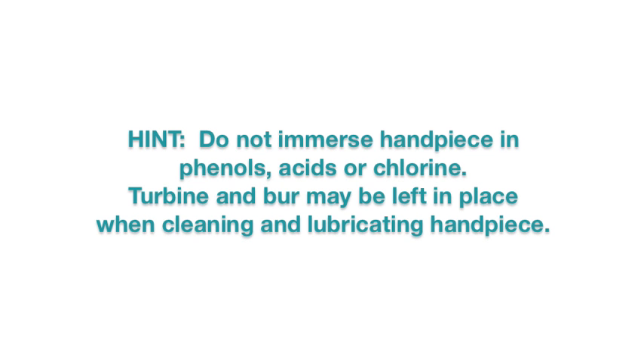Never immerse your handpiece in cold sterilant or chemical disinfectants containing phenols, acids, or chlorines. They can damage and corrode some metals.